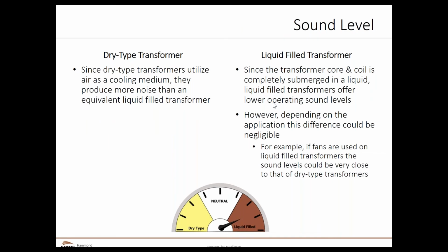Sound level. Liquid filled transformers have an advantage. We can build low audible noise transformers, but it's not our typical construction. There are things that we have to do. By taking the transformer's core and coil and surrounding it in a liquid, that does deaden the noise. Again, if you are swimming and underwater, people screaming on top of the water sound a lot quieter than if you're above it. Same thing happens with liquid filled transformers. However, liquid filled transformers often employ things like cooling fans. Remember earlier we talked about being able to build low temperature rise transformers. Because liquid filled has a lot fewer options, they may be more applicable to employ cooling fans in certain situations, and now they are more noisy. So it does depend upon the application.